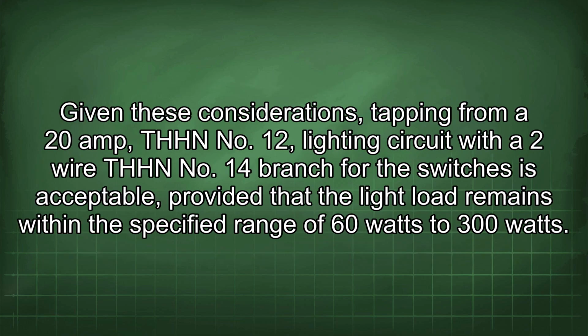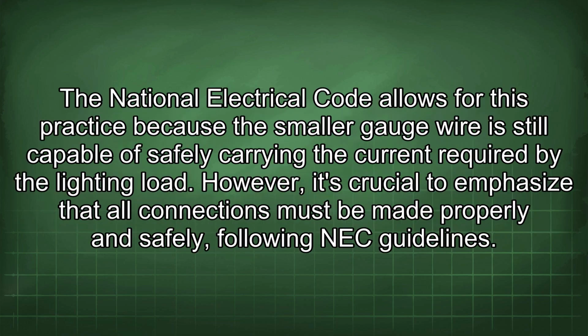wires. Given these considerations, tapping from a 20 amp THHN 12 lighting circuit with a 2-wire THHN 14 branch for the switches is acceptable, provided that the light load remains within the specified range of 60 watts to 300 watts. The National Electrical Code allows for this practice because the smaller gauge wire is still capable of safely carrying the current required by the lighting load. However, it's crucial to emphasize that all connections must be made properly and safely following NEC guidelines.